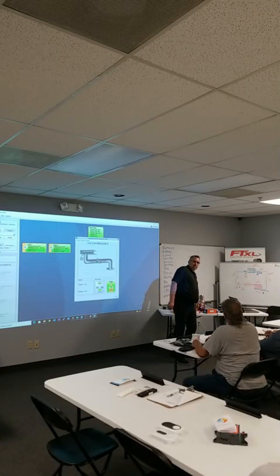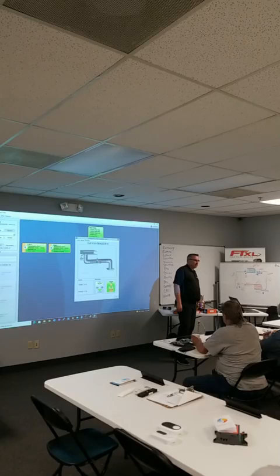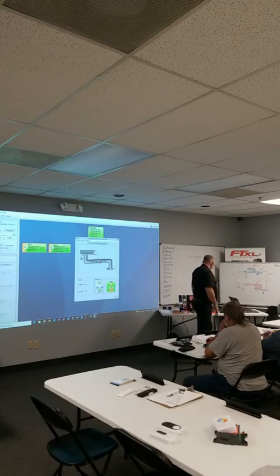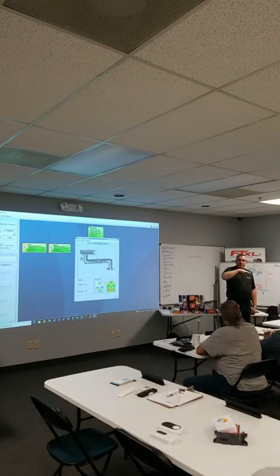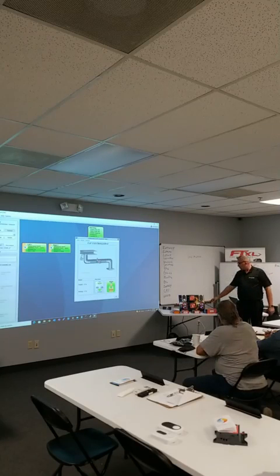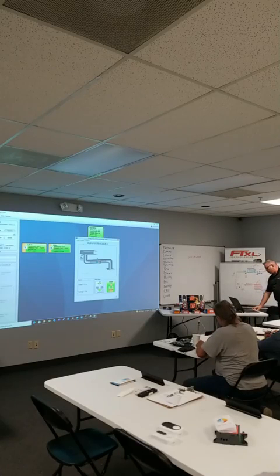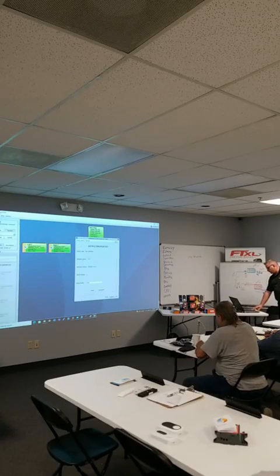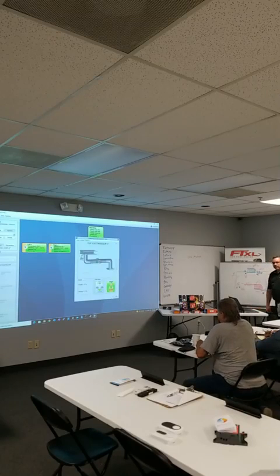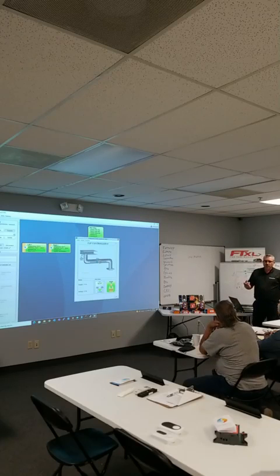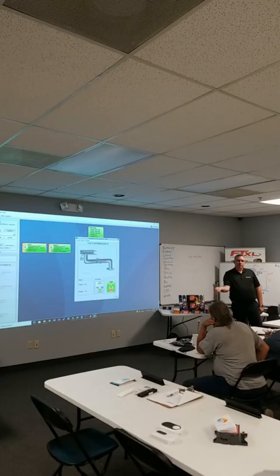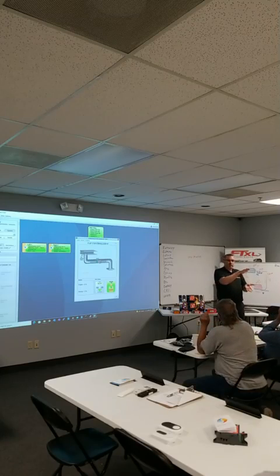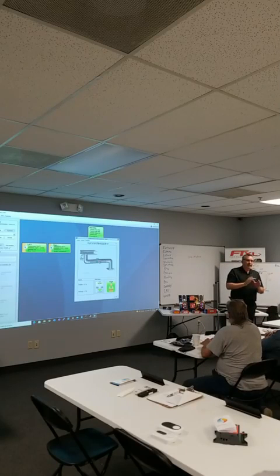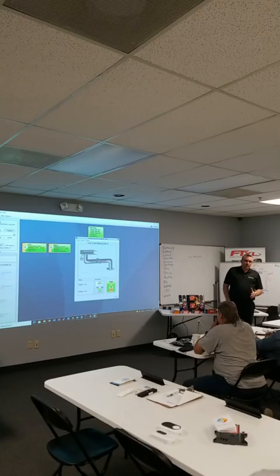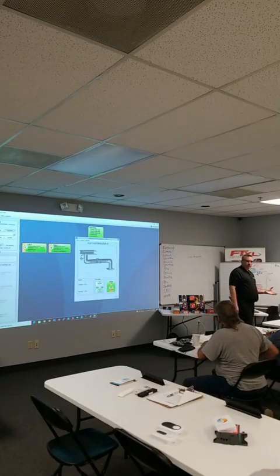These have stops, okay? Belimo has a process called adaptation that we utilize. If you put this in, 0 to 45 is 0 to 100%, and 45 to 90 is 100 to 0. You set the stops, and there are two ways to do it. You can either cycle power, or you can do a reset. The damper goes into a mode called reinitialization. It strokes all the way one way, then all the way the other way, and wherever the hard stops are, it resets its scale. In that instance, 45 degrees would be 100% open. So with that damper, if this controller set a 50% output, it would be 22.5 degrees open. Does that make sense?